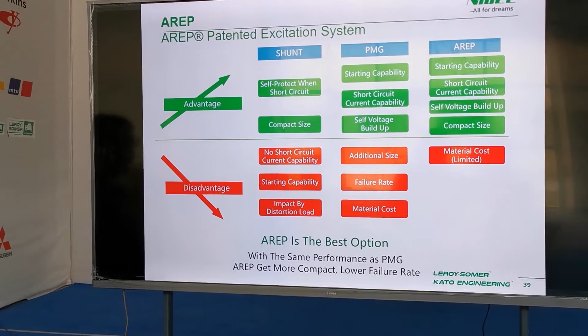So as a summary, let's do a comparison between shunt, PMG and AIP to see the advantages and disadvantages. For shunt, we normally say that PMG and AREP both have better performance than shunt, because of the starting capability and also the short circuit current capability. And the advantage of shunt is the compact size and also the better cost. So normally if the alternator runs singly, we will recommend shunt.